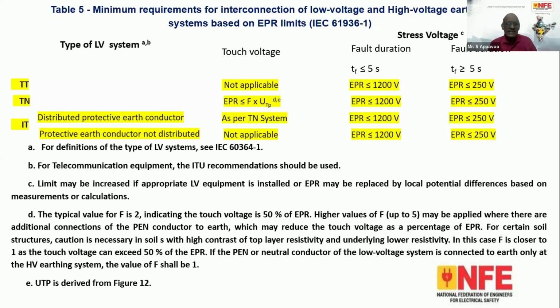So it is essential that unless we provide equipotential bonding, equipotentiality and proper interconnection of earth electrodes, it is not possible to contain it, because a very stringent norm is prescribed, but we have a long way to go to achieve this. If it is more than 5 seconds, because unlike transient voltages that occur in microseconds or milliseconds, these temporary overvoltages can occur in seconds and even more than 5 seconds. So in the worst case scenario, you have to contain the touch voltage up to 250 volts only, which is possible by interconnections and the TN-S earthing system in consumer premises as well as the equipotential bonding.